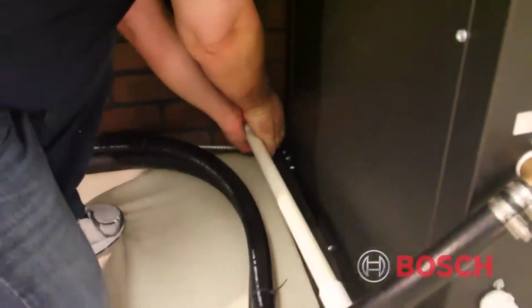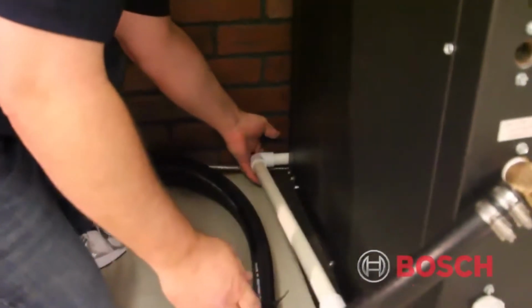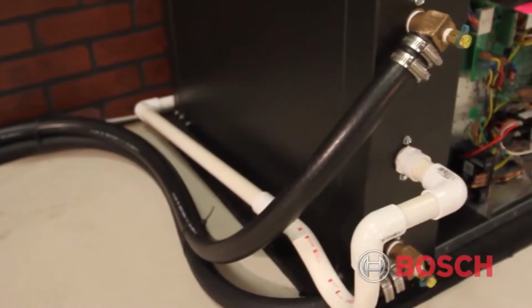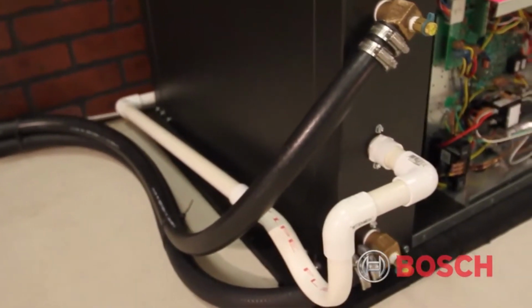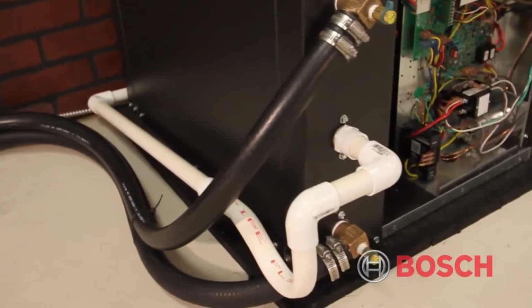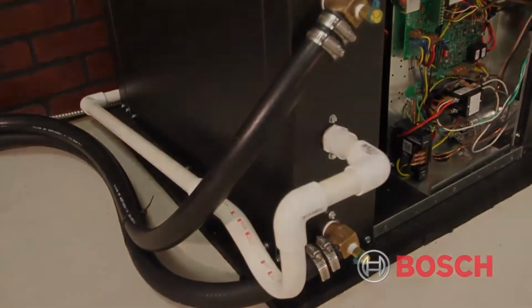You'll always want to make sure that you have sufficient slope. Usually want to follow code, but 1/4 inch per foot is a good rule of thumb to make sure you get good drain from your condensate.